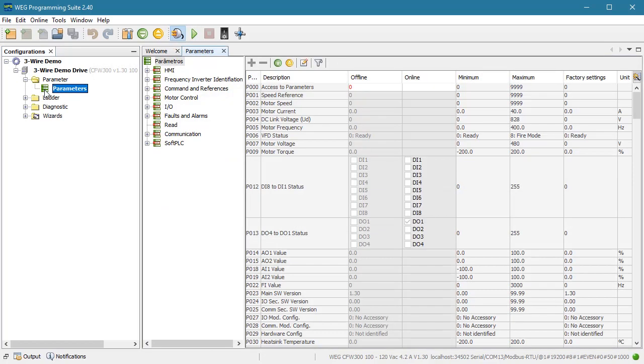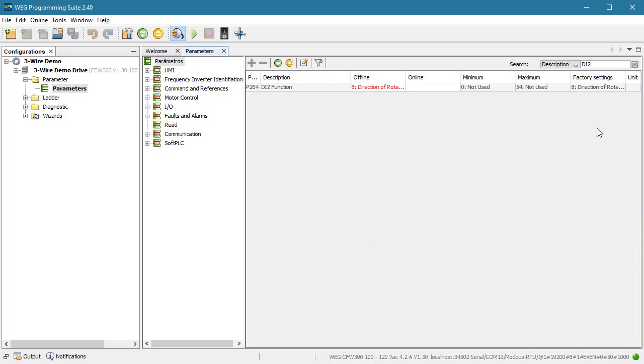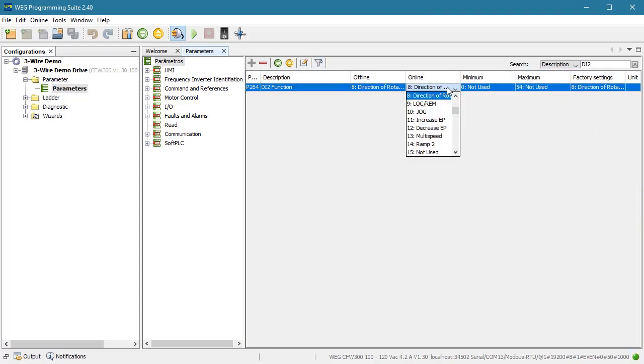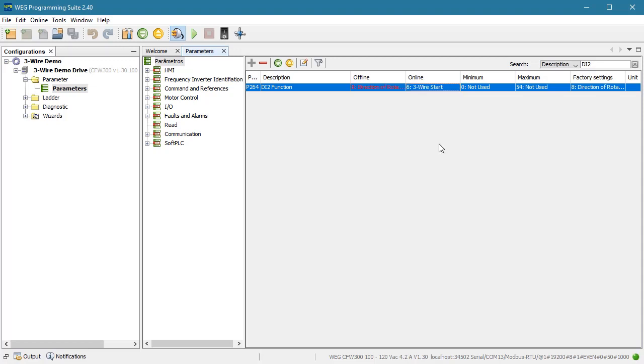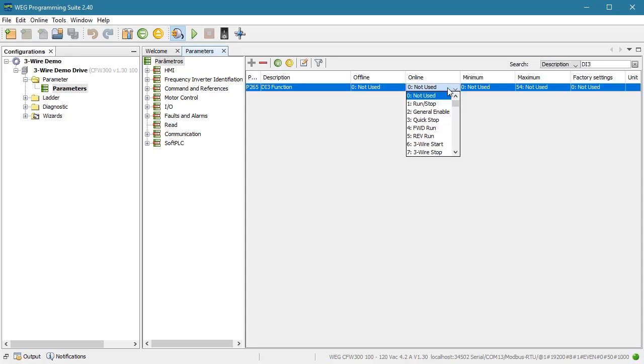Let's bring up the parameter list and search for digital input 2. Looks like parameter 264 is where we specify its function, so let's set that to a 3-wire start. Search for digital input 3 and set its function to 3-wire stop.